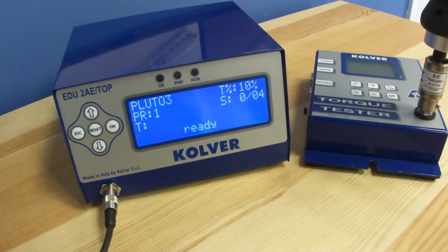Today we're going to review the calibration procedure for the EDU2AE Top Series controller. All that is needed for the calibration procedure to be complete is your Kolver system and a calibrated torque tester. For the calibrated torque tester, of course we recommend our K1 or Mini K series for best results.